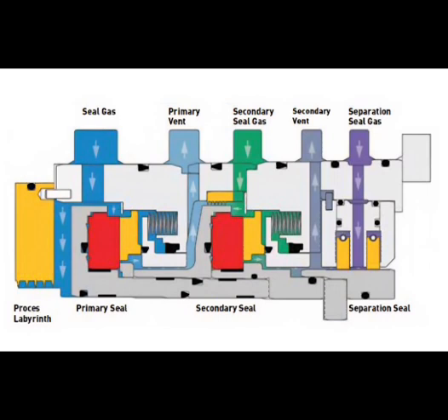The secondary vent flow is made up of the leakage from the secondary outboard seal and the leakage from the inboard section of the separation seal. Secondary vents should be unrestricted, meaning that nothing that can create a back pressure should be fitted. Differential pressures across secondary gas seals are generally small, and any back pressure generated in the secondary vent could easily reverse pressurize the secondary seal. API 692 makes provision for, but does not require, pressure monitoring and flow monitoring in the secondary vent. Pressure in the secondary vent should be at approximately atmospheric, and the flow rates through it should also be incredibly low.